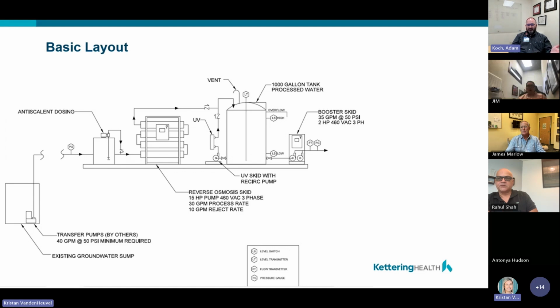There's an anti-scalant chemical that goes in to make sure those membranes in the RO system don't get jammed up. We then take the RO over to a holding tank and run it through a UV filter so it doesn't build bacteria. Then we have the booster skid that pumps it to our cooling towers.